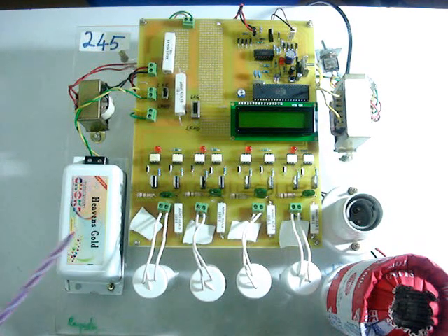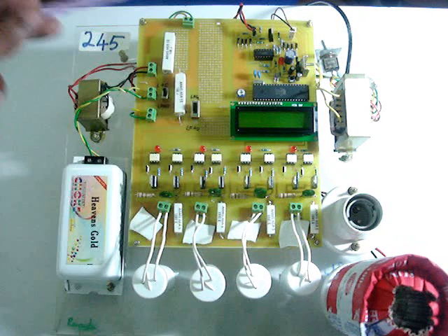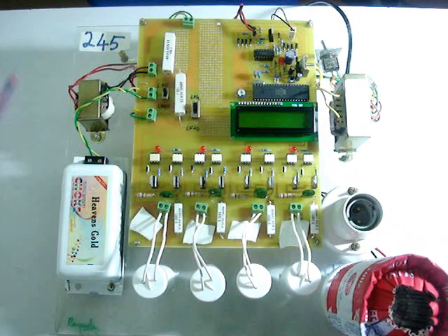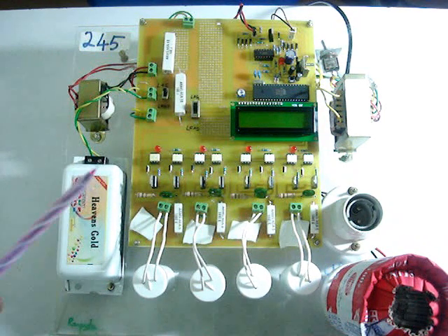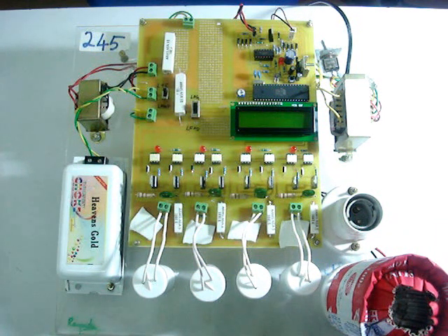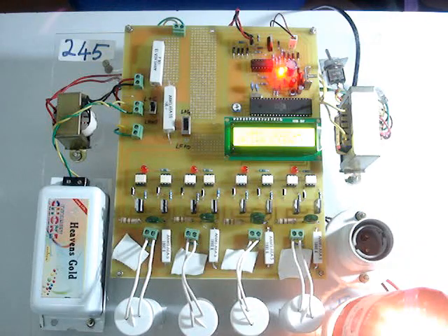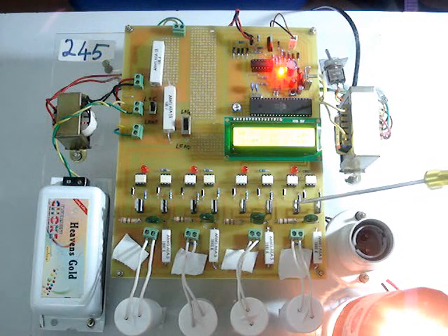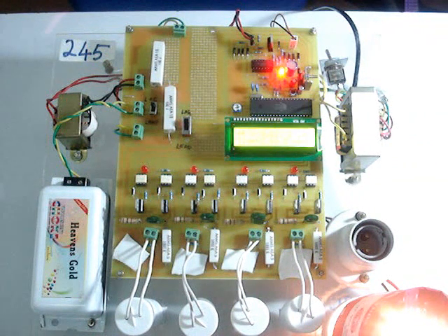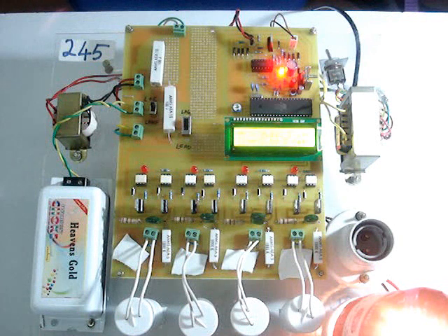Then we have a voltage transformer powering the circuit, and a current transformer to measure the current. The beauty of the circuit is that we measure the time difference between the voltage and current, and whether it is leading or lagging is displayed in our setup here. The other arrangement is a set of back-to-back SCRs, about 8 SCRs, 4 pairs back-to-back, for switching in the inductive load or the capacitive load.